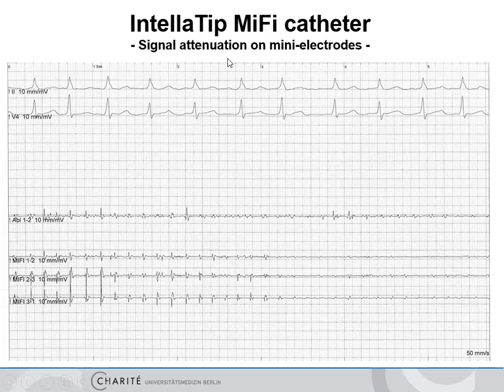This is an example of an ablation catheter which also has mini electrodes, like I showed with the mini basket - the MiFi catheter has the same characterization. You see here the tip of the catheter. This is an atrial fibrillation ablation case. Here's the signal on the tip of the catheter, and these are the signals on the mini electrodes, recorded during ablation. You see the signals disappearing on the mini electrodes, but you still have them on the tip of the catheter. So if you ablate with a normal ablation catheter, you would still see these signals, but actually you've already got a lesion at that point. These mini electrodes help you determine if you're doing a good job, or if your signals are disappearing or not, which can help you avoid perforation. You stop the ablation at the moment you see the signals disappearing - this is one benefit of the mini electrodes.